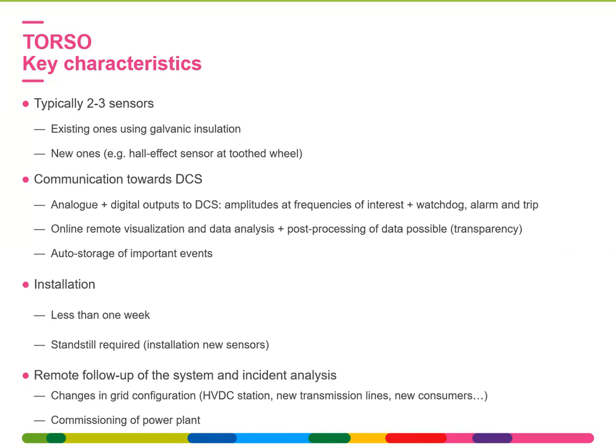Communication towards the DCS of analog and digital outputs: amplitudes at the different frequencies of interest, as well as digital outputs such as a watchdog confirming that the system is running as it should, and alarm and trip signals. Typically, the alarm signal is set below the fatigue endurance limit. So this shows that something abnormal is going on, but you're not yet consuming lifetime.